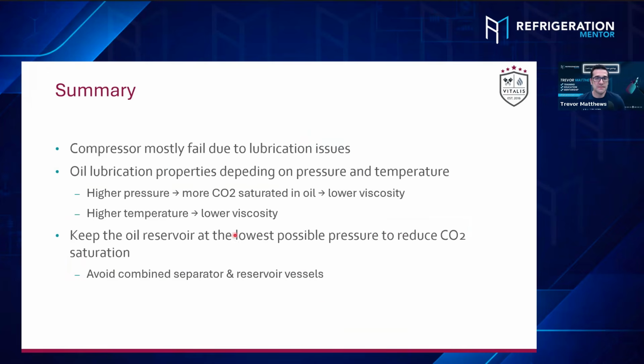Awesome. Love it. So I put a little summary together. Basically, what we've talked about today: compressors mostly fail due to lubrication issues, which are either liquid-caused or general oil-caused because of the storage conditions or the refilling conditions. Higher pressure always saturates more CO₂ in the oil, which lowers the viscosity, which we want to avoid. And the same goes for higher temperatures, which also create a lower viscosity.